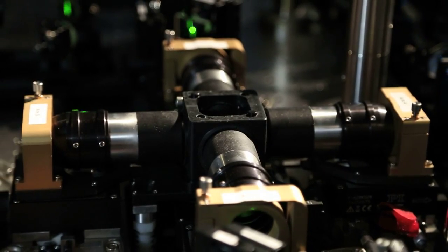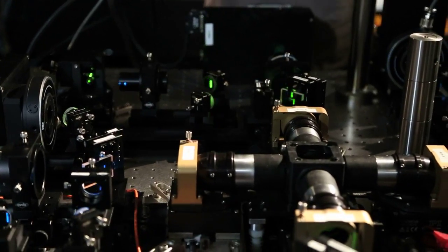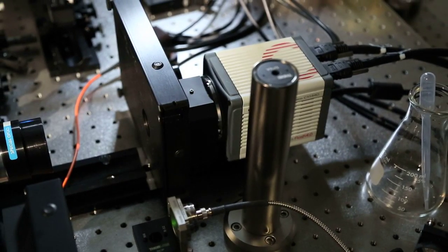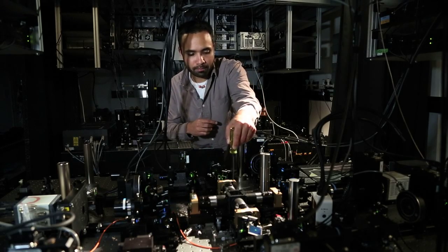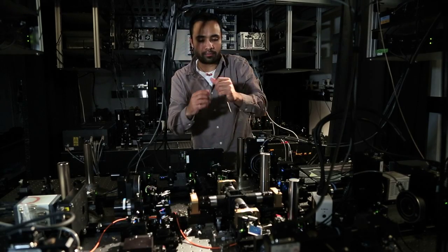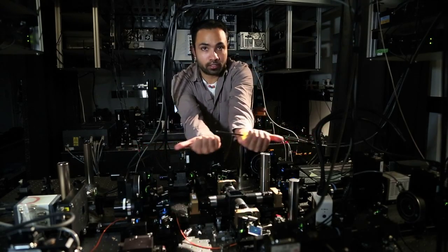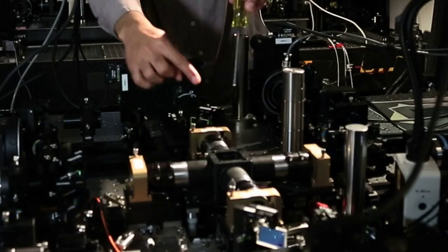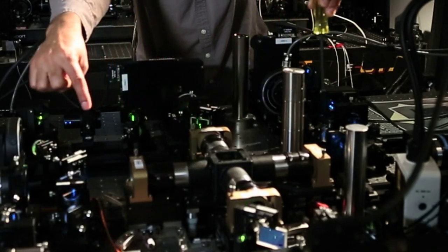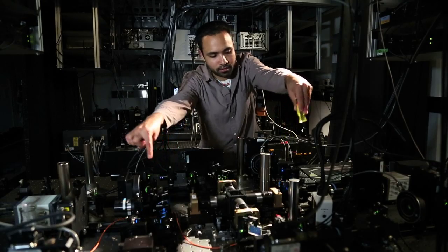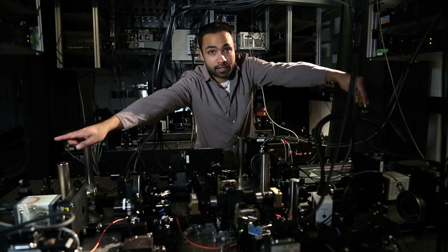Once that light hits the sample, it excites fluorescence in the sample. That fluorescence is collected by the cameras in the orthogonal directions. For this laser light that's going through to the chamber onto the sample, it illuminates the sample, and now the fluorescence is emitted in all directions. Those two cameras are now collecting that fluorescent light. The light path for detection would be these two objectives, past these dichroic mirrors, past the tube lens, past the detection filters onto the camera.